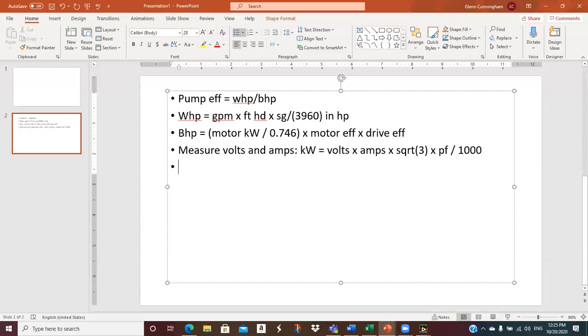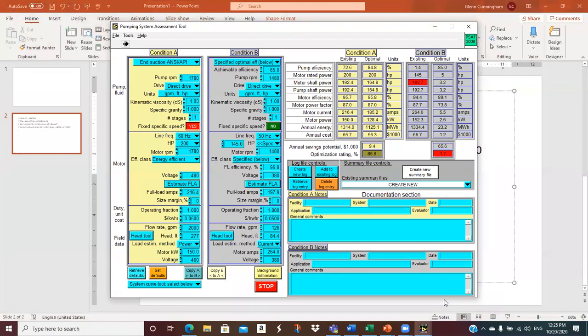So, there you go. Now, let's go back to PSAT, and let's check this. But see, PSAT's going to do all this for you. Now, let me get out my calculator. And so, we got, what, 2,000 GPM times 277 feet of head. And specific gravity, this is just standard water, so it is 1, divided by 3960. So that's about 139.9 horsepower. Store one. I don't think it gives you that number. Okay, but we've got 150 kW.